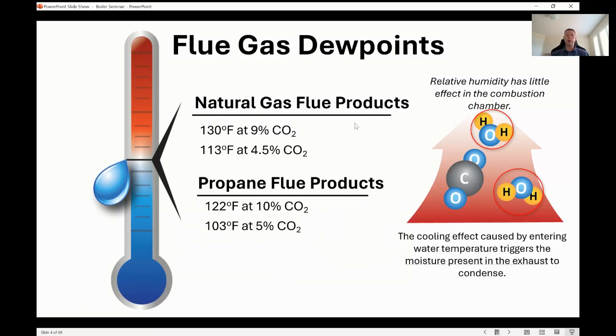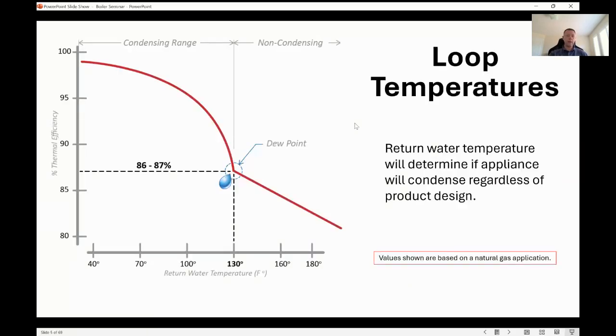So with an atmospheric product, you can actually have a lower return water temperature before you have to deal with condensation. As I said, it's all basically about that dew point, and I'm going to stick with fan-assisted combustion, natural gas from here on in. So that magic number is 130 degrees. So anytime you're operating above that, you're in non-condensing mode, and you're going to have a combustion efficiency of around 86, 87%. Anytime you operate below that, you're in condensing mode, and you're going to potentially condense in there, and you're going to have a boiler and a stack that can handle that.